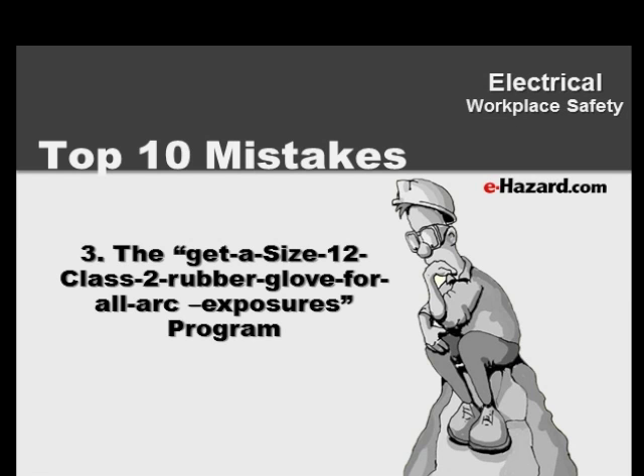Another problem we see is people go out and they say, okay, let's get a Class 2 size 12 rubber glove for all of our arc and electrical exposures. What happens in this kind of situation, these kind of programs, is they just try to do a worst-case scenario program. We went out to a plant not too long ago.